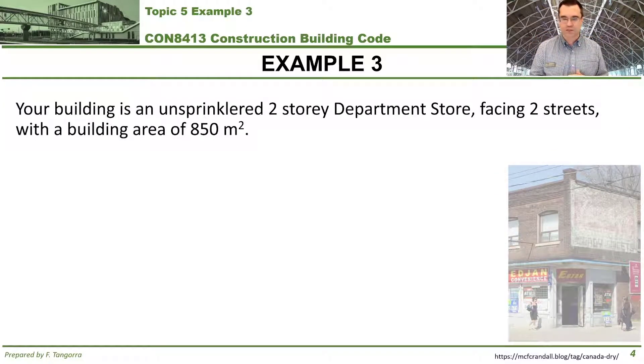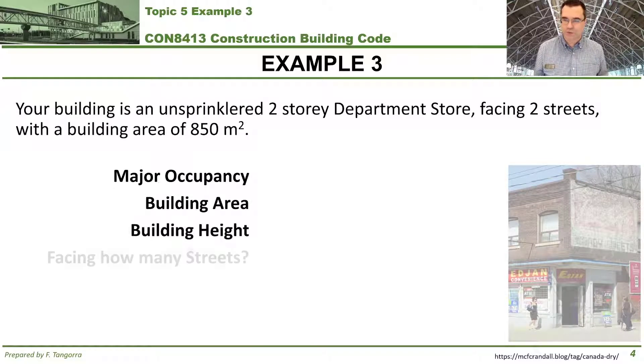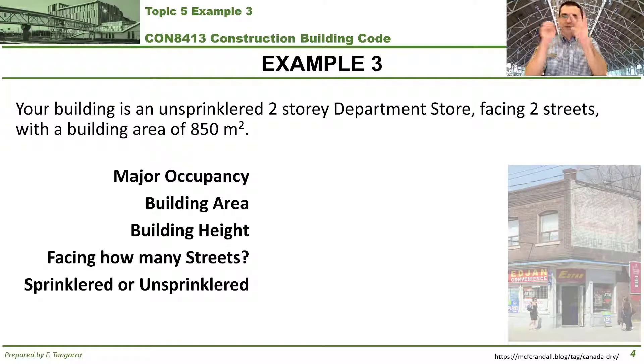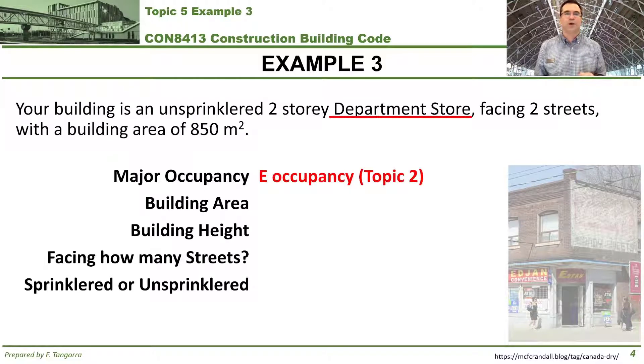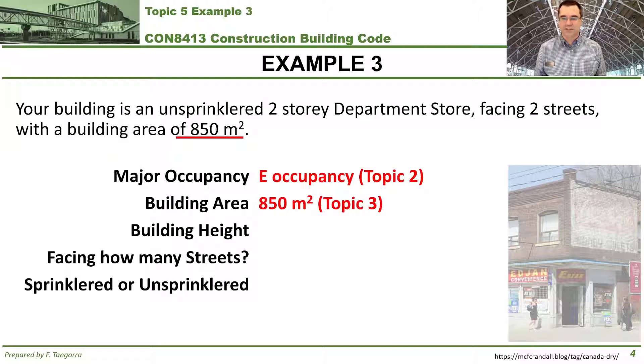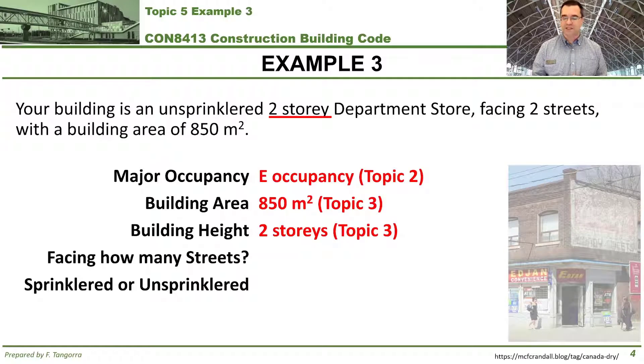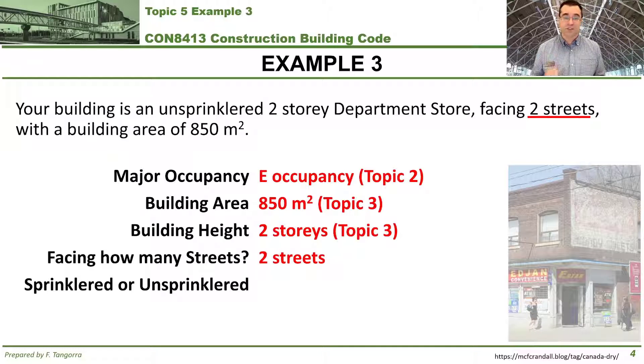Let me rearrange the important information to use the rest of the screen to solve this question. We're going to use the same five building characteristics previously identified and pluck out the information from this example. What is the major occupancy? Because it's a department store, our knowledge from Topic 2 tells us it's an E occupancy — Appendix A is your friend. Building area: 850 square meters. Building height, as we learned in Topic 3, is the number of stories — in this case, two stories. How many streets is it facing? Two streets. And is this building sprinklered or unsprinklered? It's unsprinklered, meaning there are no sprinklers in this building.